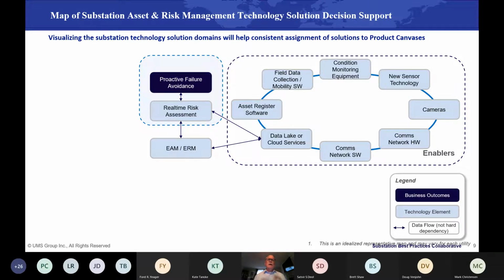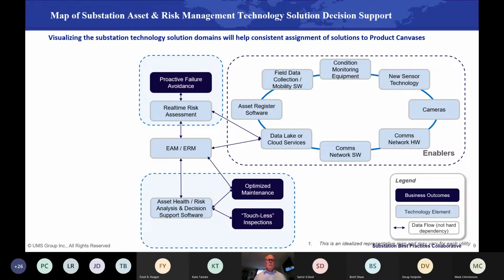So if I'm looking at nine gases, acetylene, ethylene, methane, et cetera, I may be well below the threshold but trending up, and being able to forecast that in 7 days this is going to break that lower threshold, and in 15 days it's going to be something I need to think about taking out and mitigating. Those are vitally important elements to doing asset risk management more effectively.